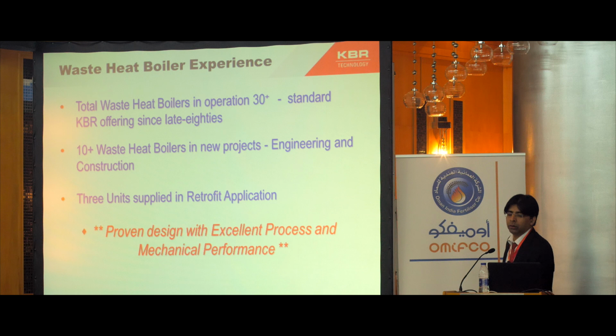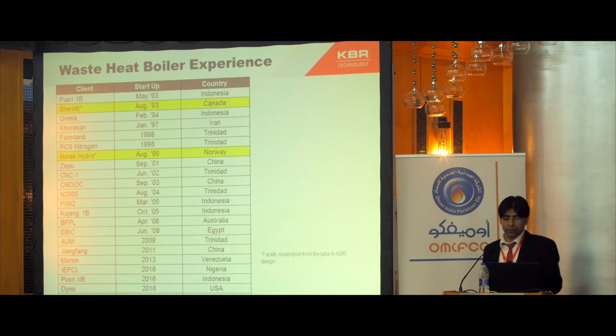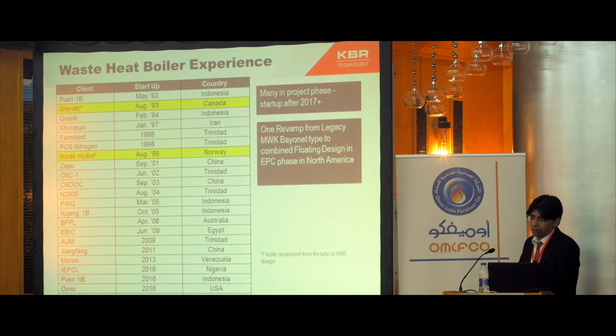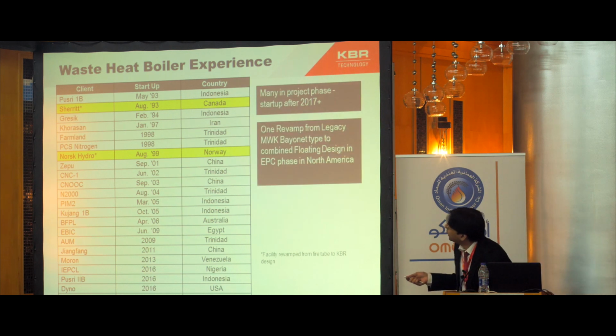We have these total waste heat boilers, 30 plus boilers which we have been using. There are 10 plus waste heat boilers in new plants which are undergoing engineering and construction. We have supplied 3 units in retrofit applications. It's a well-proven design with excellent process and mechanical performance. But this is our experience with the waste heat boiler. It is worth noting that Sherrit and Norsk Hydro both have the fire tube design, which were revamped with the KBR floating head design. One of the revamps from MWK Bayonet design to floating head is currently in the EPC phase and will probably come online in a year or 2.